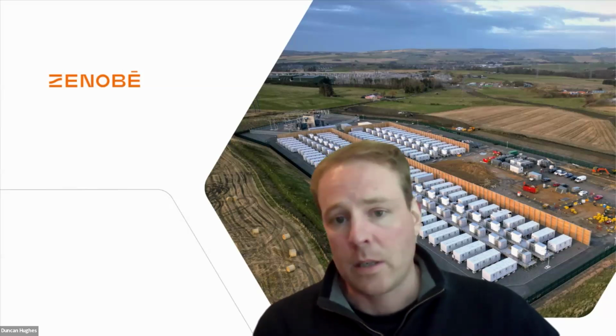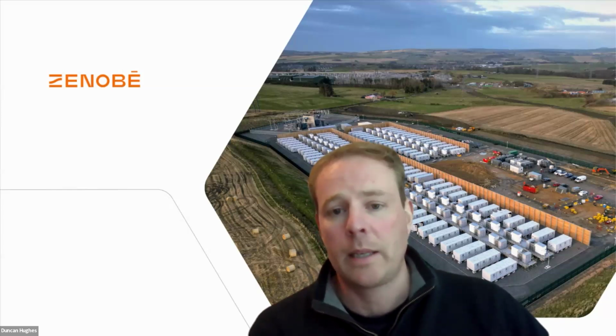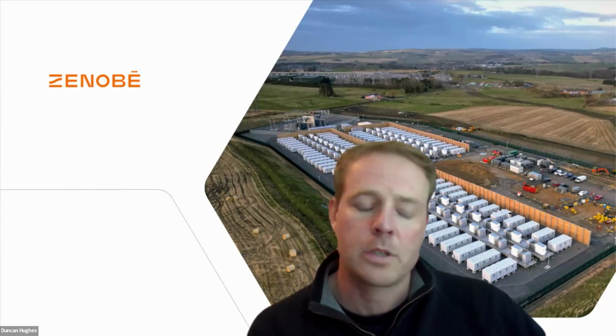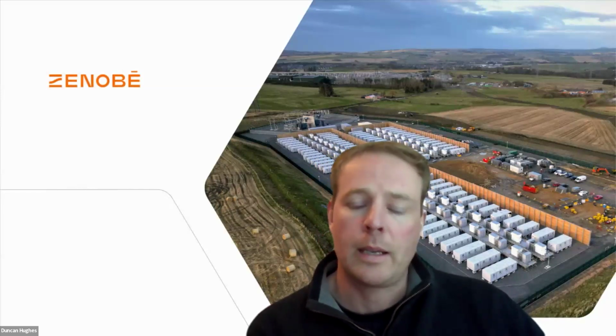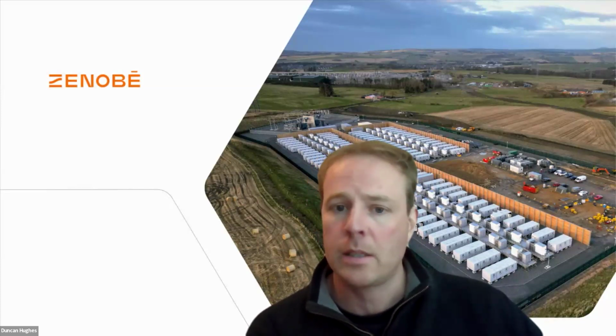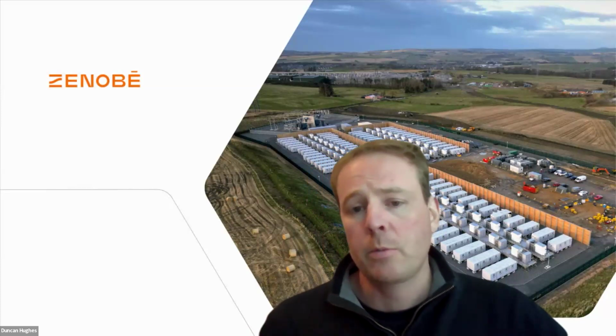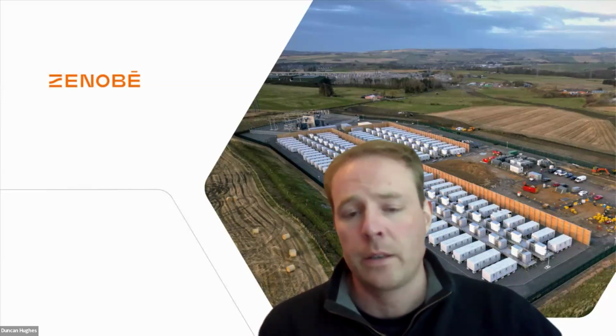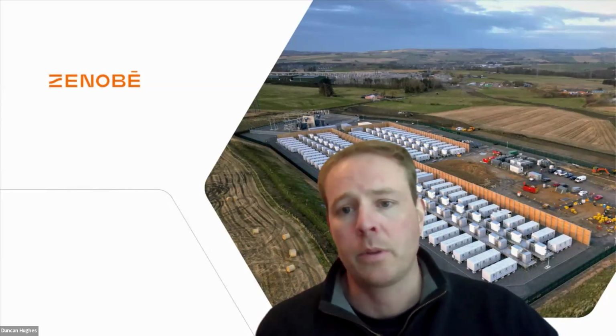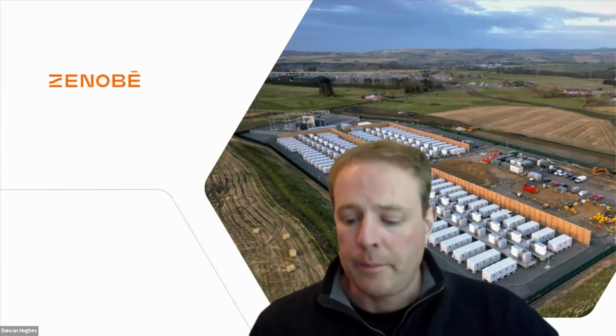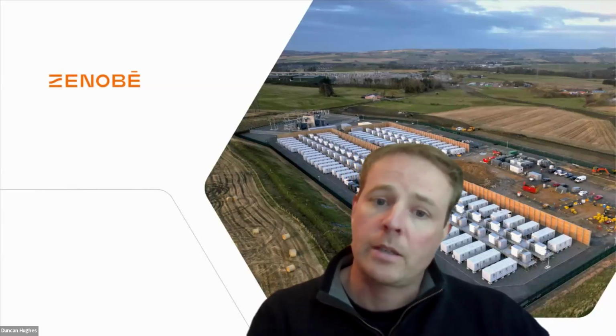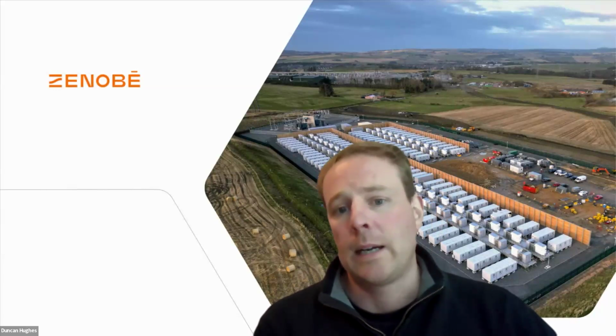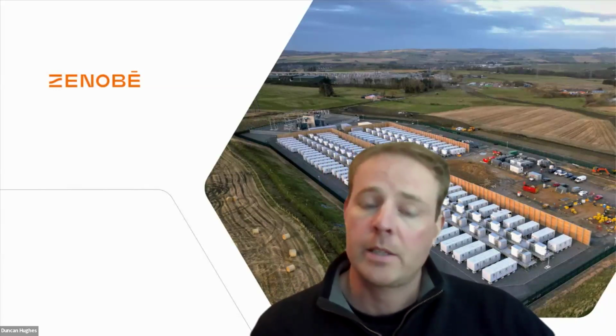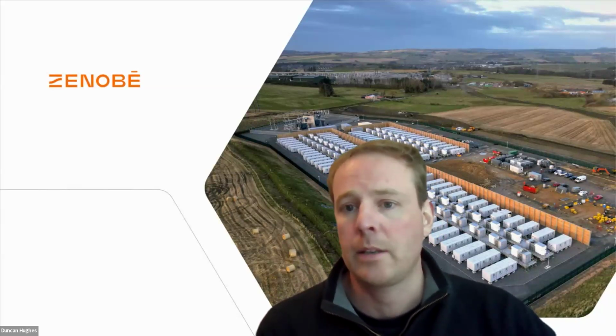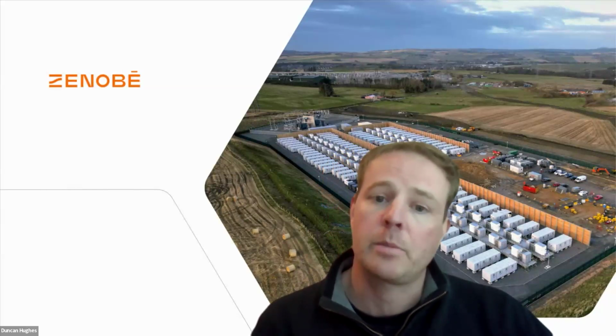So the answer to that is no. When we talked earlier about how we sized and optimized the plant, and looked at the overload capabilities we could leverage, it's been done such that even when the plant is operating at maximum import or export levels against its rated 200 megawatts, it will still provide all the inertia we're contracted to provide under our SP2 service. That's done by exploiting the inherent overload capabilities within the inverters. We were very keen not to restrict our trading opportunities in order to provide these services, and what we landed on lets us have our cake and eat it, in terms of the technical support we provide to NESO and the flexibility we retain within the market.